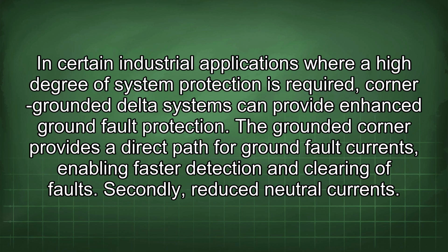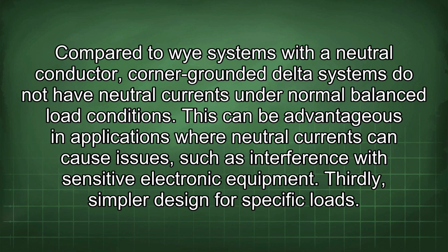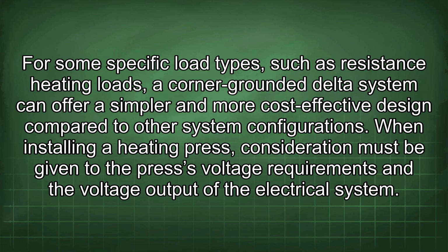Secondly, reduced neutral currents. Compared to Y systems with a neutral conductor, corner-grounded delta systems do not have neutral currents under normal balanced load conditions. This can be advantageous in applications where neutral currents can cause issues such as interference with sensitive electronic equipment. Thirdly, simpler design for specific loads. For some specific load types, such as resistance heating loads, a corner-grounded delta system can offer a simpler and more cost-effective design compared to other system configurations.